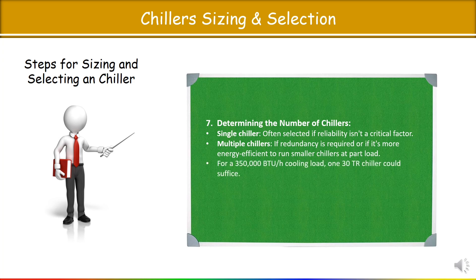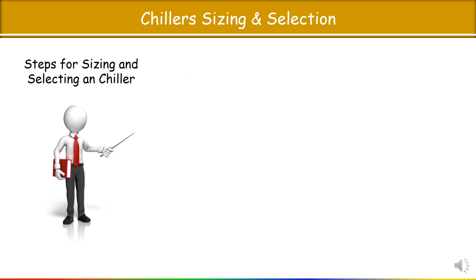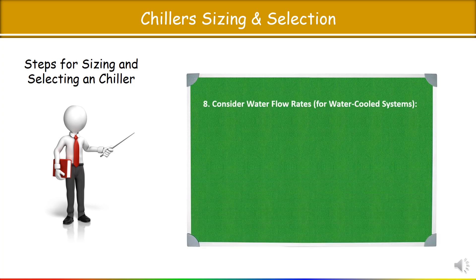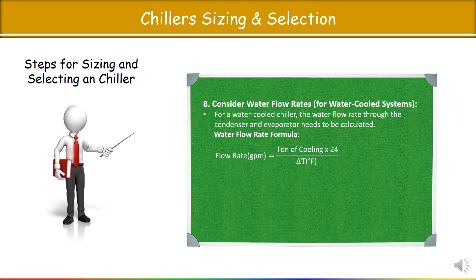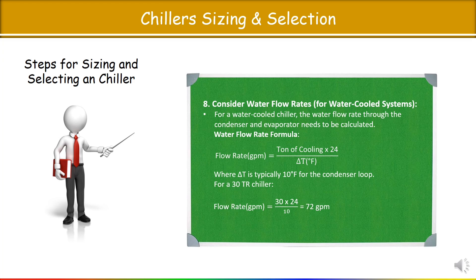For example, for a 350,000 BTU/hr cooling load, a single 30 TR chiller would suffice. However, for redundancy or efficiency at part load, you might select 2 × 15 TR chillers. For a water cooled chiller, the water flow rate through the condenser and evaporator needs to be calculated. The formula is: Flow Rate (GPM) = Cooling Load (TR) × 24 ÷ ΔT. Assuming ΔT = 10°F and chiller capacity = 30 TR, you get a flow rate of 72 GPM.